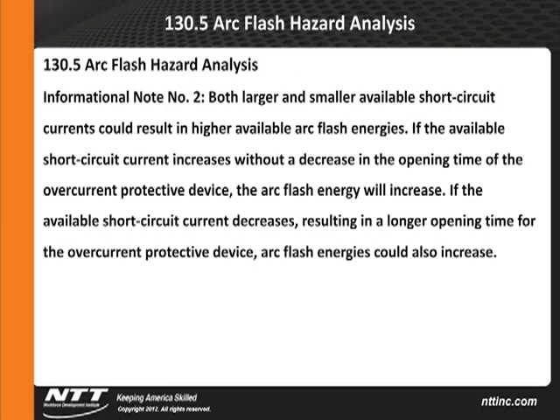Arc flash analysis, an informational note. And this is, again, where we've got to look at the reality of where we work. Both larger and smaller available short-circuit currents can result in higher available arc flash energies. If the available short-circuit current increases without a decrease in the opening time of the overcurrent protective device, the arc flash energy will increase. I recently had an individual call me up and say, Larry, when I was running my arc flash analysis at this particular area, I only ended up with 8 or 9 cals. But when I changed it to this, and it was a lower amount of short-circuit current, I ended up with a higher number. Why? Because your overcurrent protective device may not clear. If the available short-circuit current decreases, resulting in a longer opening time for the overcurrent protective devices, arc flash energies could also increase. So this helps us further clarify how we go about doing calculations and the results.